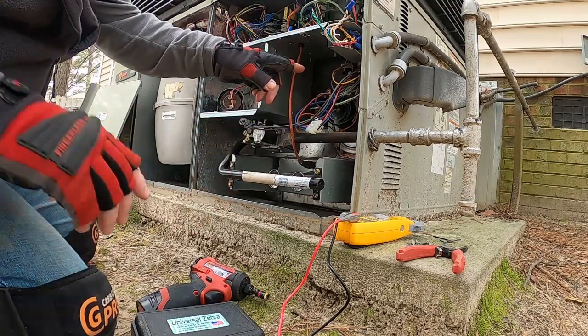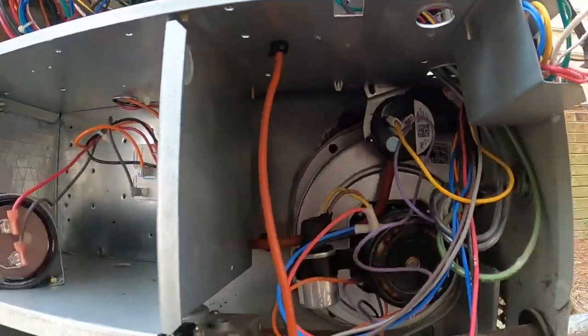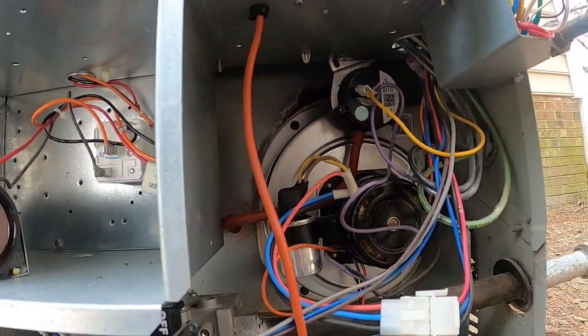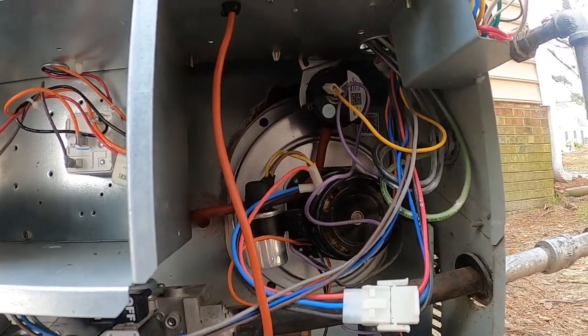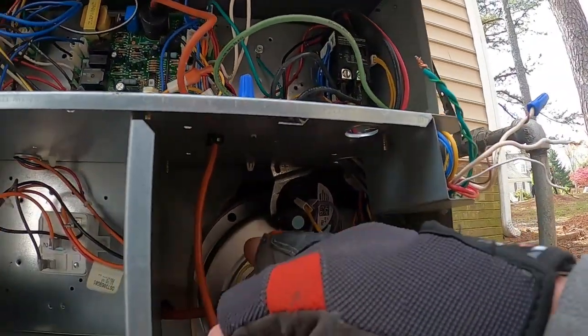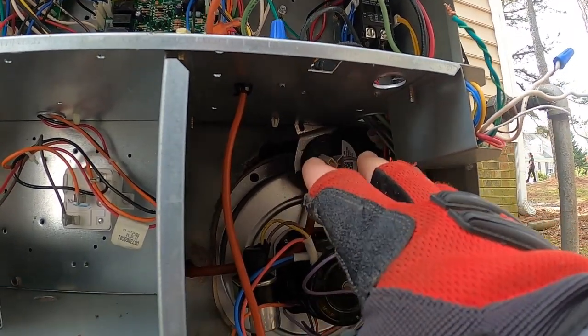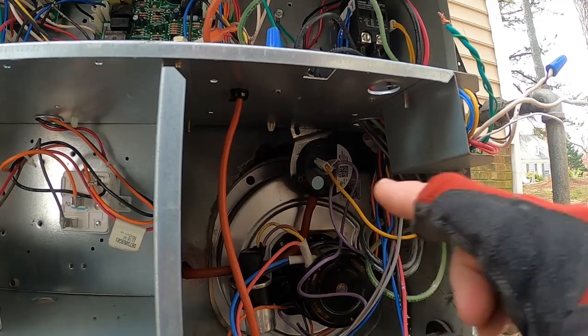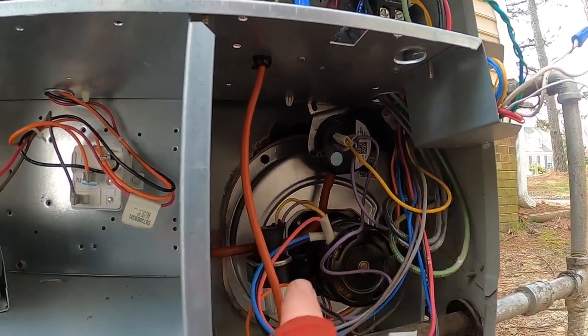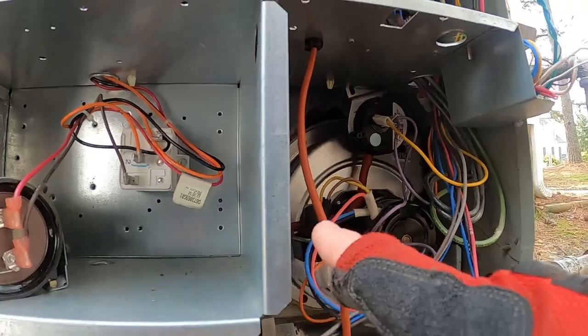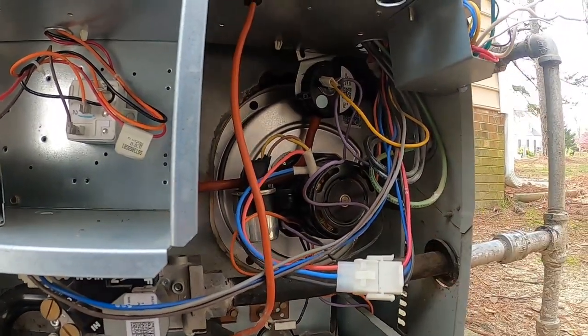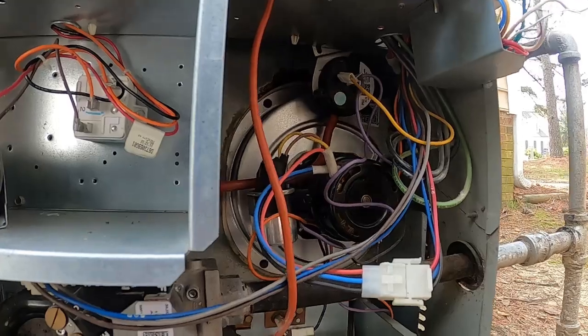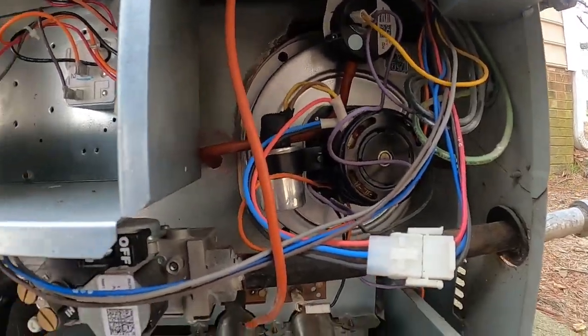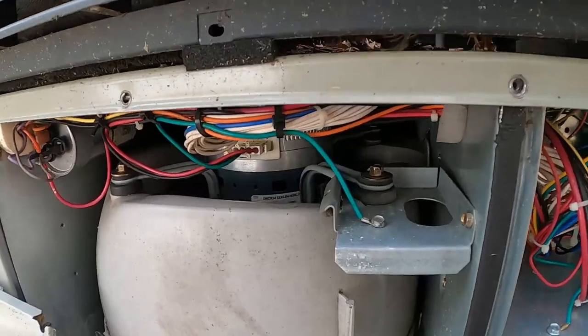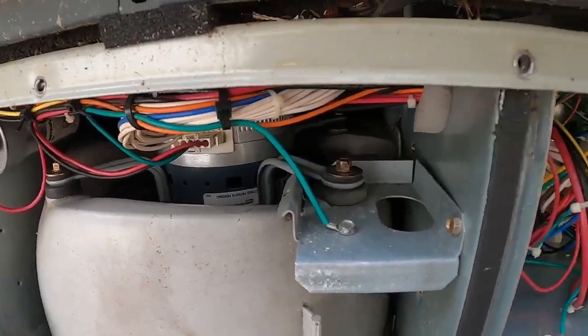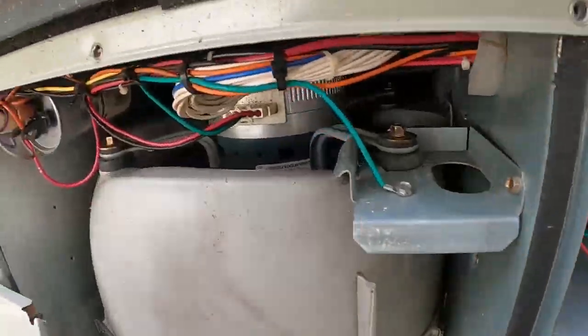So what I did is I disconnected the hose in here, reset the breaker. Then I came back, gave it a call for W1 at the thermostat wire with the hose disconnected so that the pressure switch wouldn't be closed on startup. And then it started to go through its test sequence. Then I put the hose back to the pressure switch to simulate the system closing the pressure switch normally after the call for W, and it fired off. But I sat here and the blower motor never came on. I energized G and the blower motor never came on.